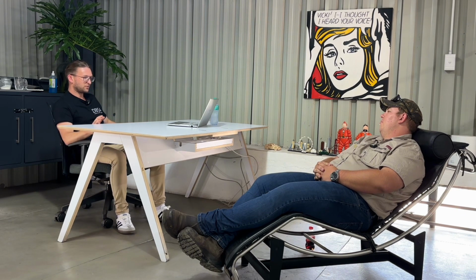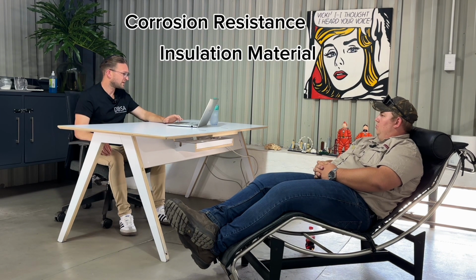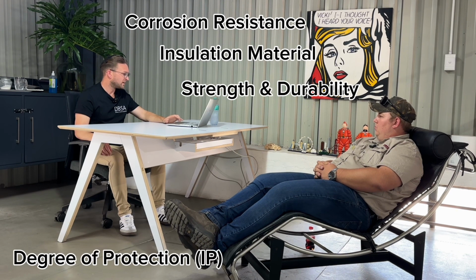So you think that, okay, once you've type tested, then you've got type tests for everything. But there's obviously a range of type tests. Start off from the beginning of type tests. Actually, you have to go according to a code, which is 61439. And to get it fully type tested, there's a whole bunch of tests within type testing. We have a list of them. There's corrosion resistance, insulation of material, resistance, strength and durability, degree of protection, dielectric tests, temperature rise.